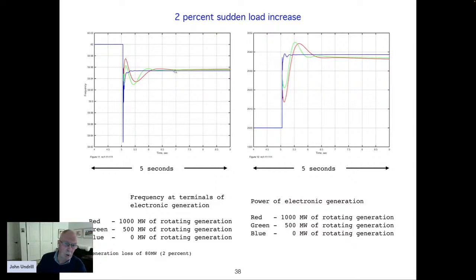And secondary control would bring it back up over the next 2 minutes, perhaps 3 minutes. Here's what the electronic power needed to do in order to stabilize the system. If the rotating generation was 1,000 megawatts, this is the power of the electronic generation doing what it needs to do with a little bit of help coming from the rotating generation. If there's a lot of rotating generation, 1,000 megawatts, the electronic power needs to follow the red line.